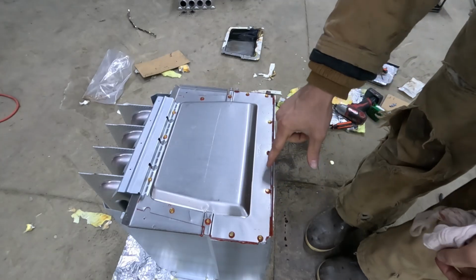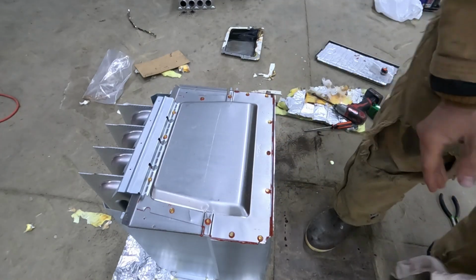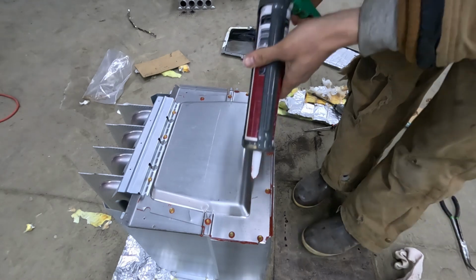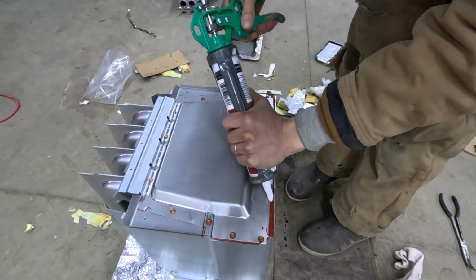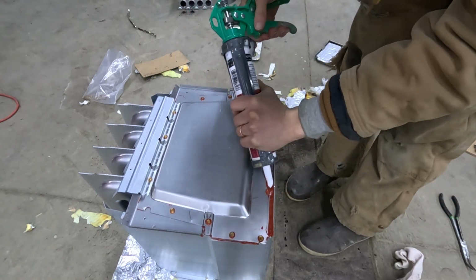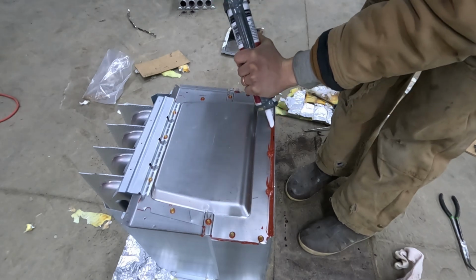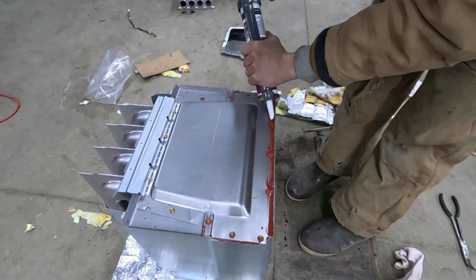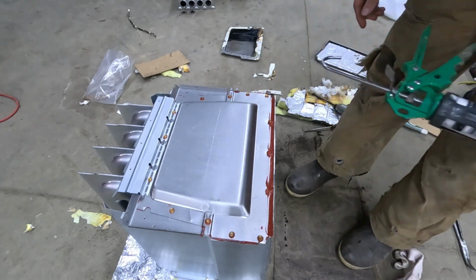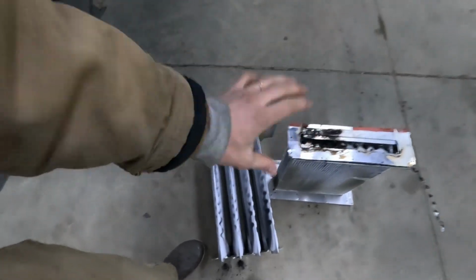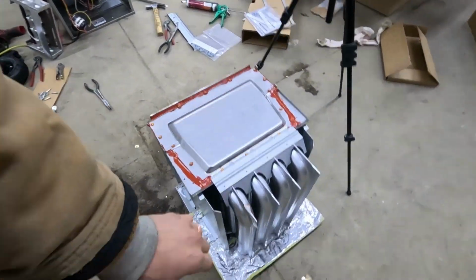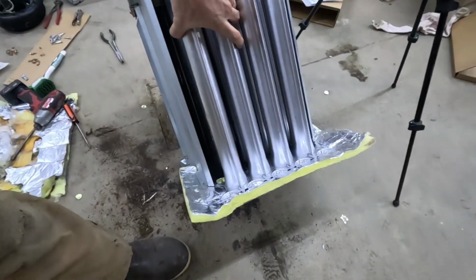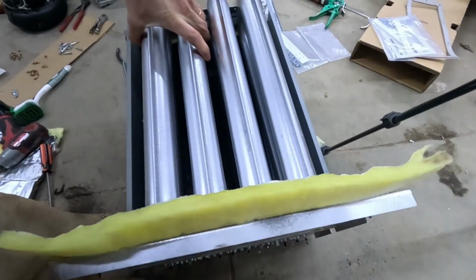Since it's common for them to leak on this bottom edge here, I think it's a good idea to run a little extra high temp silicone into this crack right here, because once it starts leaking it will start eating away the metal. So that's the primary and secondary out, and the primary and secondary put back together. Just examine this one more time.